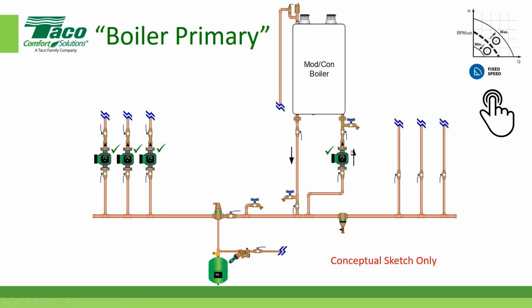All we're telling people to do here is really sharpen your pencil when it comes to that universal hydronic formula calculation, the same one we did right at the beginning of the first session. And let's just do something. I'm going to pull my phone out, and I want you to pull your phone out as well and get to the calculator version. We'll do something really simple here. Let's take a 150,000 BTU boiler. It could be 155 if that's the increment you're used to. So I'll use 155, 1, 2, 3 zeros. And I'm going to use the shortcut version of somebody sizing a pump on this application. I'm going to divide it by 20, and I'm going to divide it by, let's say, warm water at 490. What did you get? You got 15.8, didn't you? That's what I got anyway, and that sounds right to me.